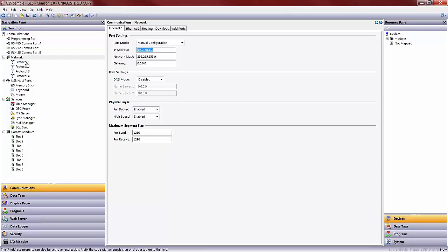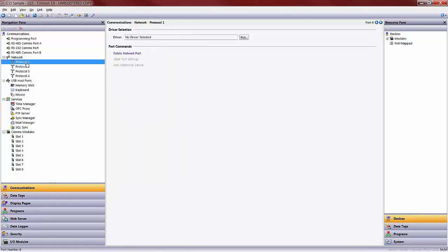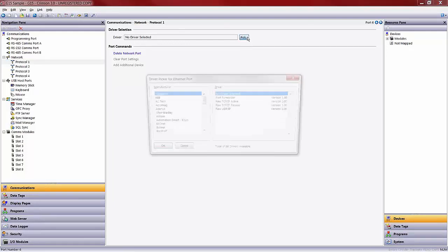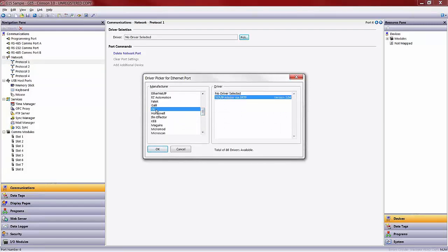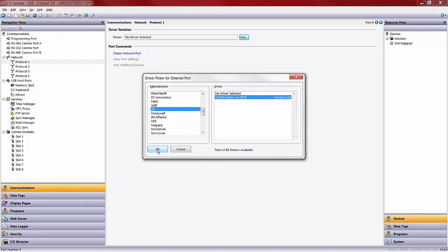For this, I will click on the protocol 1. From here, I want to go to my driver selection in my workspace window and pick, under manufacturers, my GE driver. As you can see, the GE driver listed here, for those familiar, is GE's proprietary Ethernet protocol, SRTP. I will go ahead and select that.